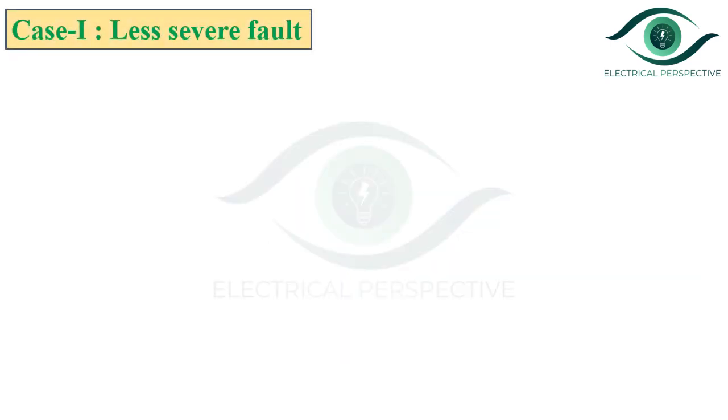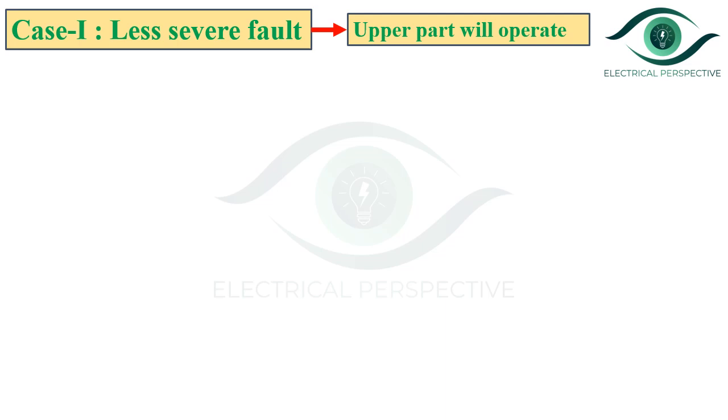Now let us discuss the operation of the Buchholz relay. We have seen that there are two elements. The first one is the upper element, which closes the alarm circuit in case of less severe fault, and the second one is the lower element, which closes the trip circuit of the circuit breaker in case of severe internal fault. Let us consider two cases. Case 1 is the less severe fault, so obviously the upper part will operate.